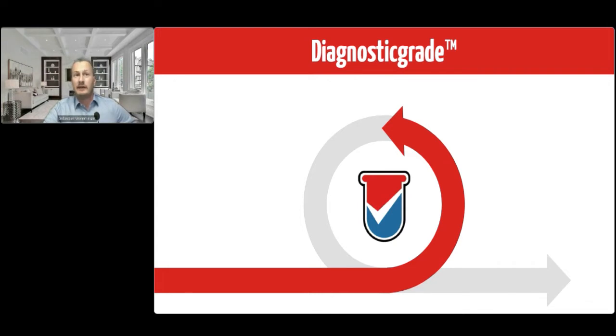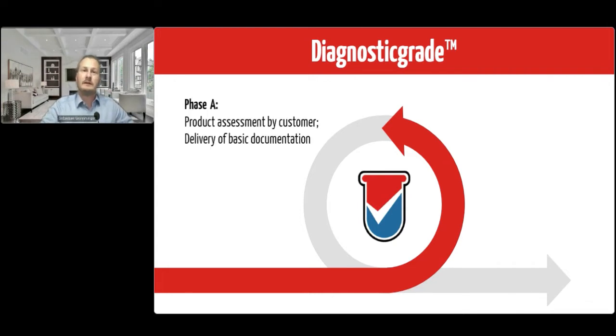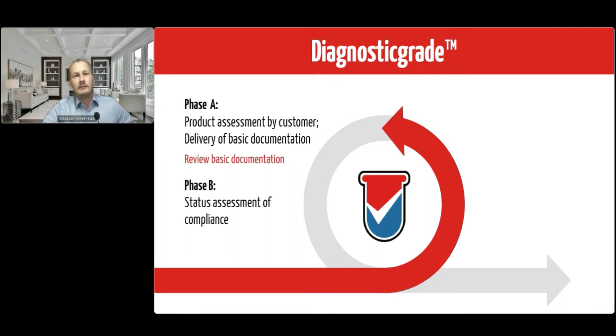And in a phase A, so to say, the products can be assessed by the customer, so by the laboratory, and delivery of the basic documentation takes place by the supplier. And what Jona Institute could add on that is to review that basic documentation and provide you evidence that this is in compliance with IVDR. And in a phase B, a status assessment of the compliance can take place with a gap analysis and supplier audit so that the laboratory exactly knows what to do to reach the compliance for the whole laboratory service.